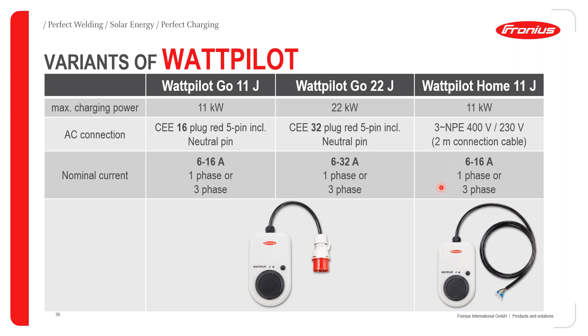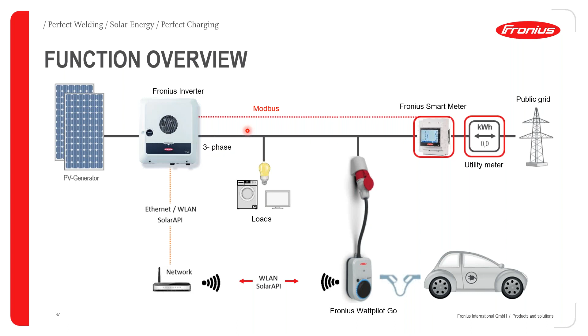This is a functional overview of how you would wire your Fronius Wattpilot. So you'll have your PV generator, your Fronius inverter, also communicating via a Fronius Smart Meter, and you'll have your Wattpilot Go or Home version connected in your system itself, and it will be monitored via network to communicate via the Fronius Wattpilot and with your Fronius inverter. It'll be the same if you're using a hybrid or a normal grid-tie inverter. It's exactly the same, even if it's 3-phase, so whether you're charging over a single phase or 3-phase.